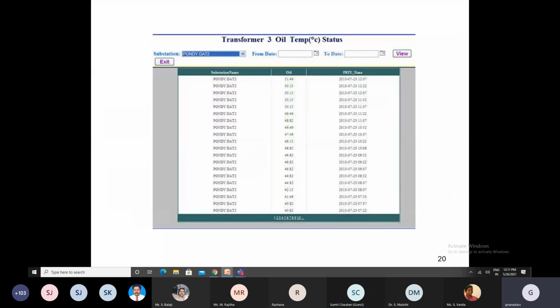Yeah, this is the snapshot about the oil temperature. So how is the oil temperature monitored in the case of our smart grid here? The oil temperature will withstand up to 90 degrees. If your oil temperature is greater than 70 degrees, it will intimate the substation in the case of the transformer. So if anything goes wrong with the transformer, any unbalancing load or overloading condition, or any internal fault or external fault in the transformer, oil temperature is the first point where it is reflected. Oil will get heated if the windings are heated. So monitoring the transformer oil using a float, and remotely communicating the data to the control center, is a vital point to monitor the data here.